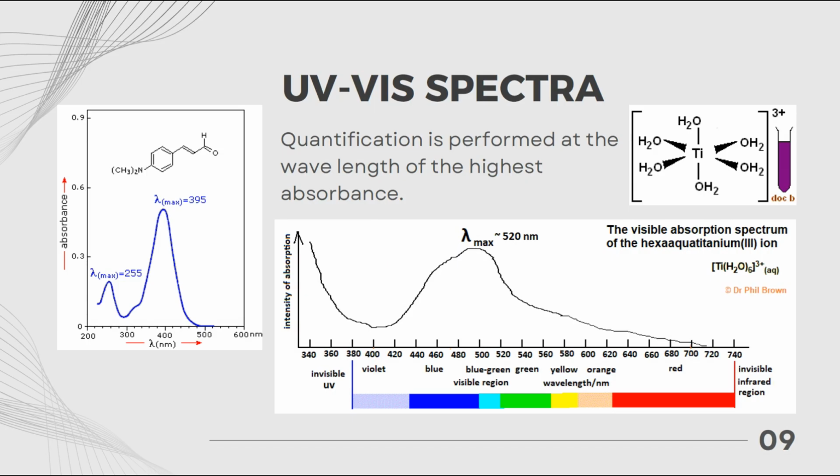You understand, if you select some wavelength here, of course it is possible, but you have no space to go down, because if you decrease the concentration, the peak height will go down in the same proportion, under the same ratio. So that's why we logically select lambdas with the biggest absorbance values.